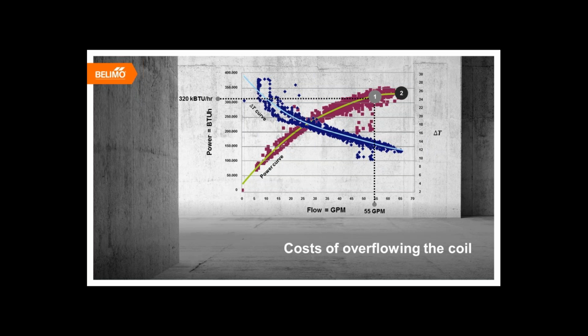Point 1 is a flow of 55 gallons per minute and equates to a 320 kBTU per hour rate of power. Point number 2 is a 65 gallon per minute flow through the same coil, which equates to a 325 kBTU per hour increase in energy.